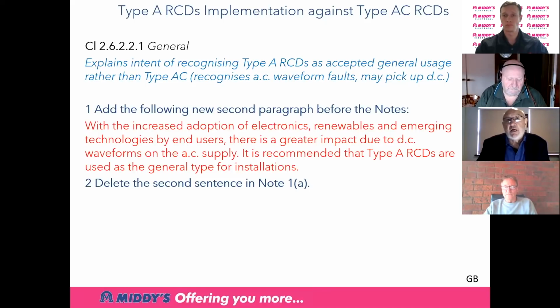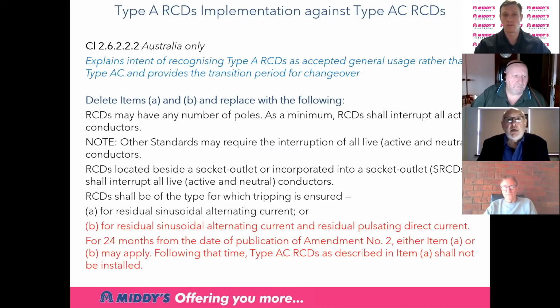So now we're going to make type A RCDs, which are for both AC and DC waveforms, so we can pick up any earth fault that may occur in both alternating current and direct current. And so what we've done is those red words there is what we've added in to explain why we're bringing in type A RCDs. And if we move on, yes. So what we've done is we've made a few changes within the clauses as written there, 2.6. What we've added in there is that it should be for residual, sinusoidal, alternating current and residual pulsating direct current.